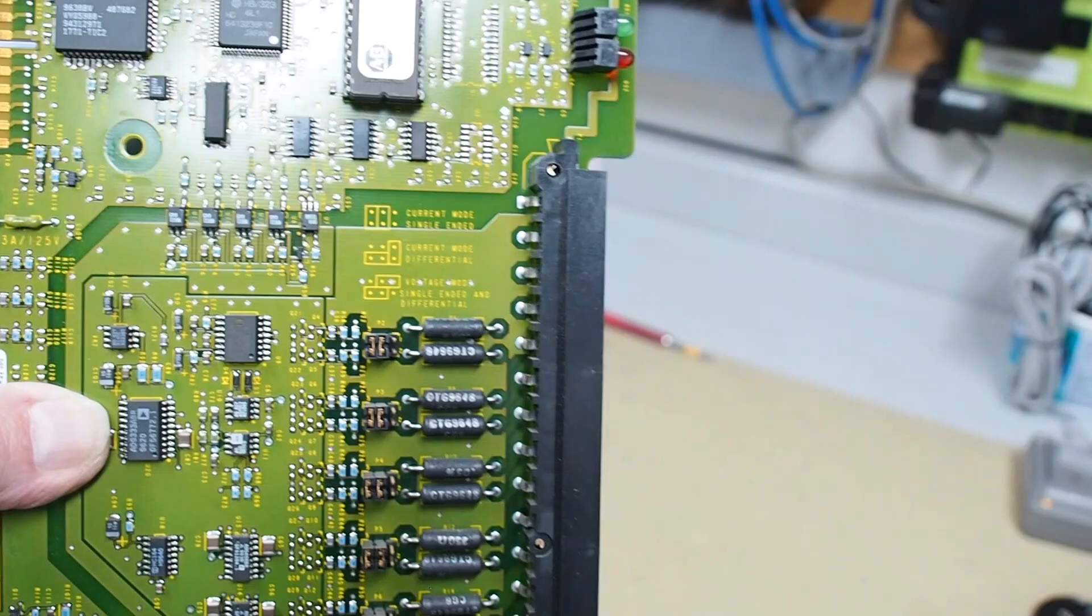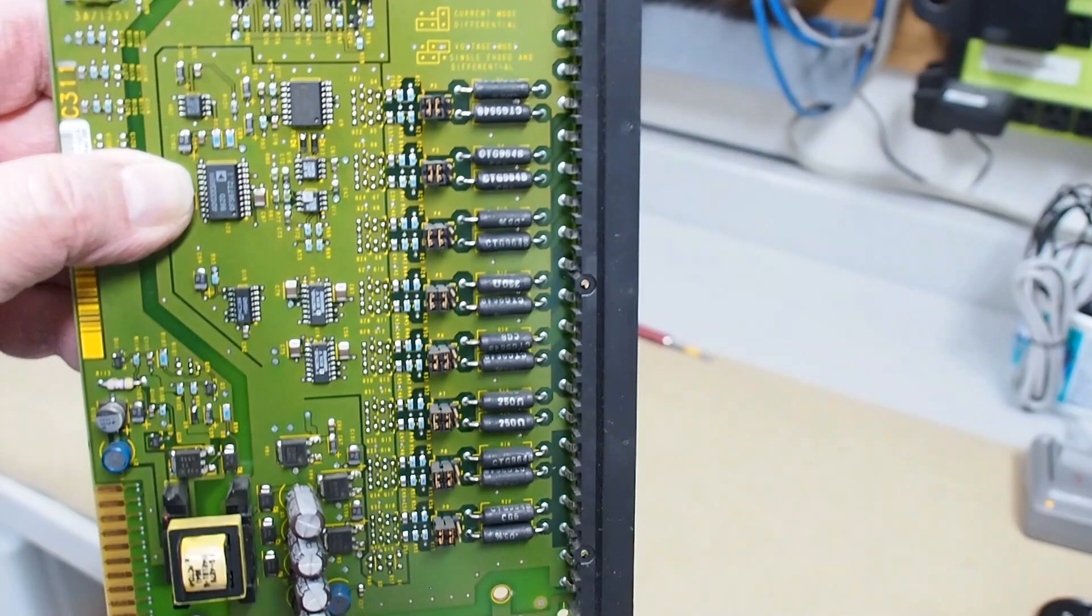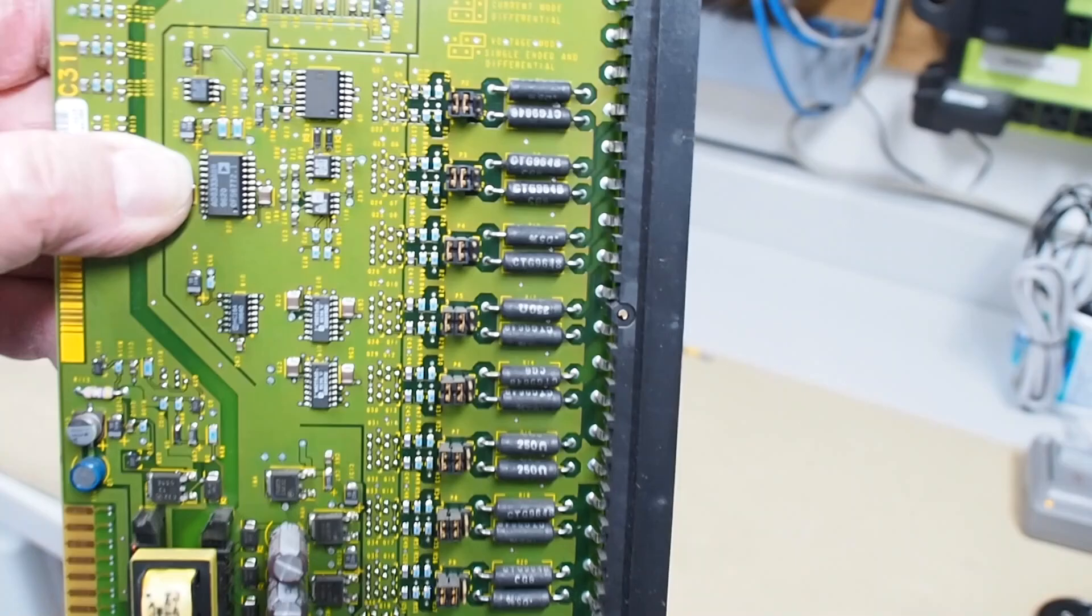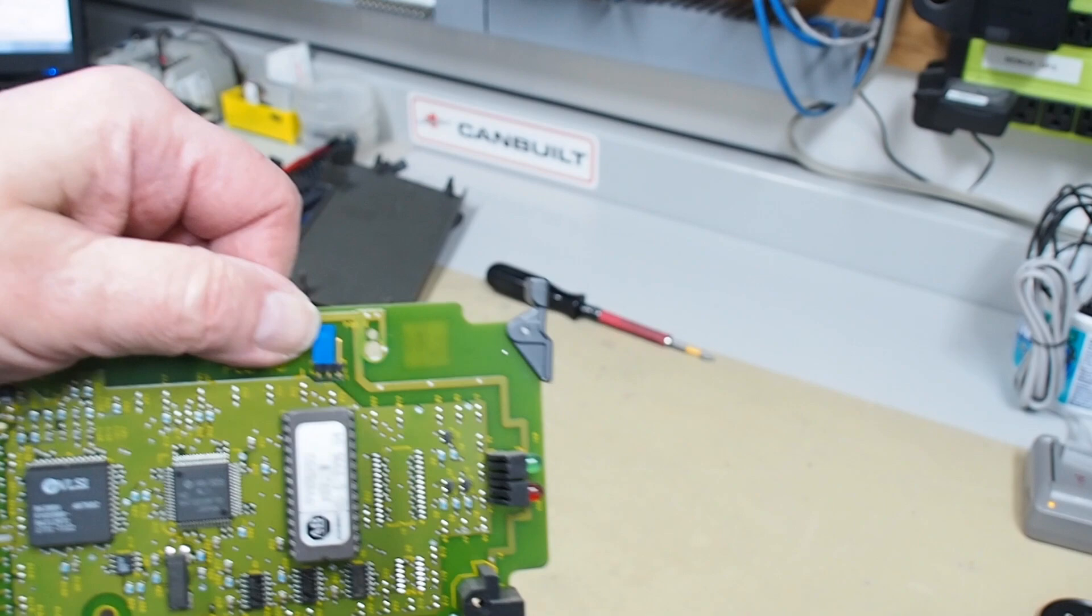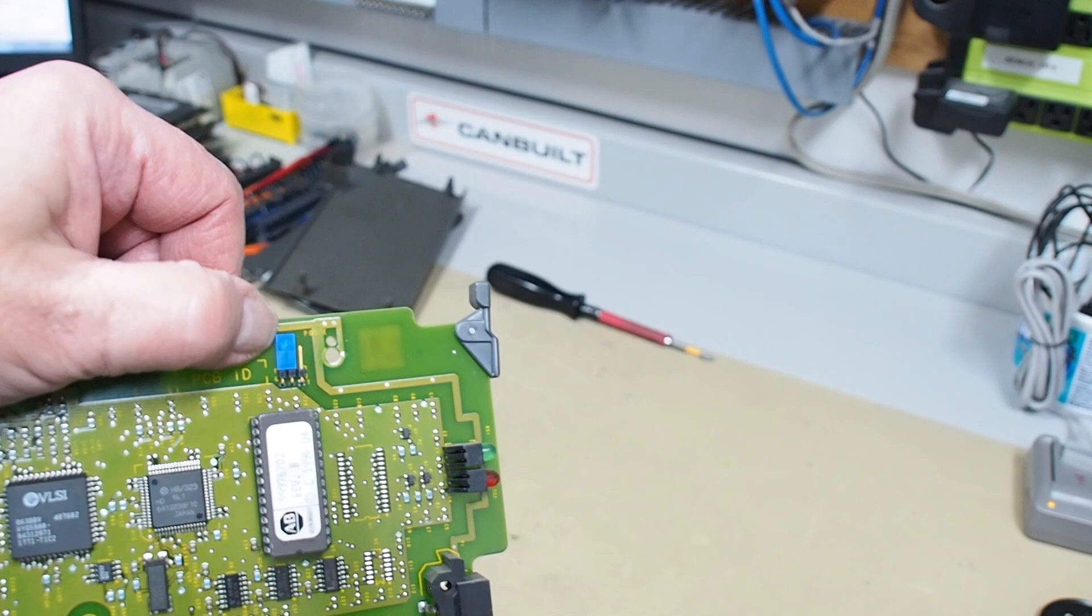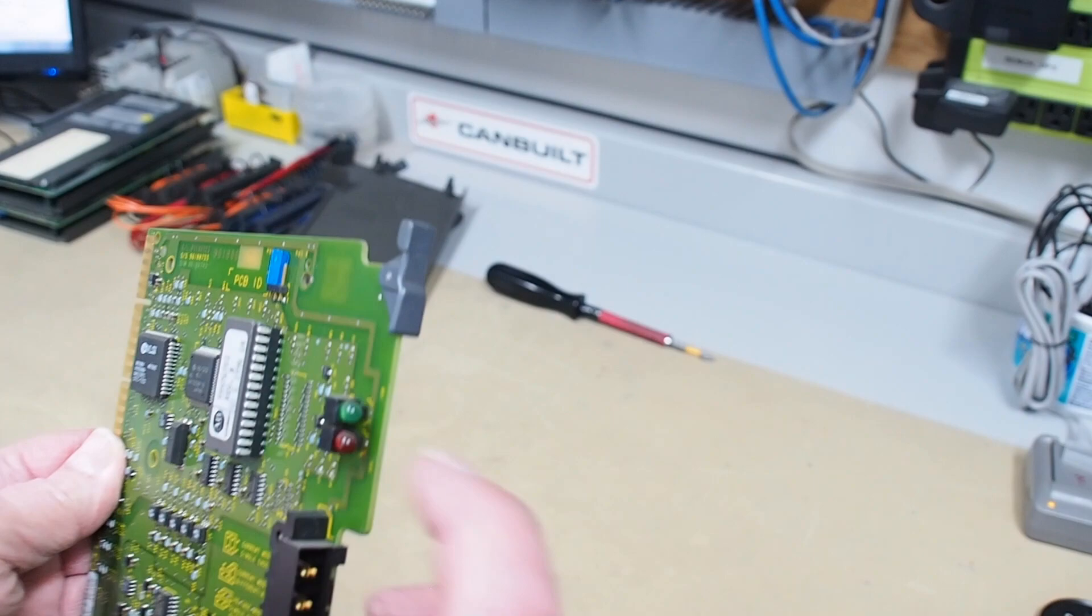Generally, in most applications that I've ever seen, it's either current or voltage, single ended, to give you the 16 channels to work with. As you can see, this card has four capacitors in it, it's got a little transformer, all kinds of little stuff, and there's a jumper at the top here for emulating older systems, so this could be used with a PLC2 if there's any left out there. The documentation, which is available online, explains what that does. There's your run light, your fault light, and your terminals.